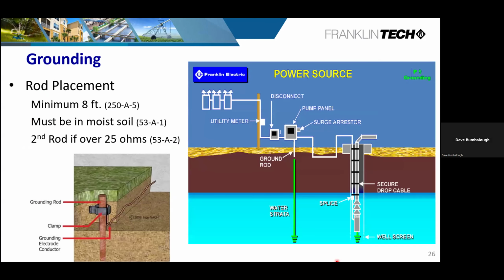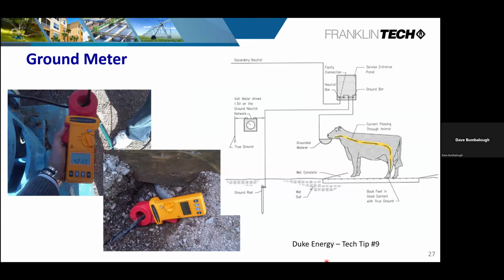So, proper grounding. I always try to make sure that there are ground rods out there, and that clamps are actually clamping and not broken or missing. Again, what I try to point out here is that our submersible pump casing is in a water strata. That's the best ground rod you're ever going to have. We don't want that. We want to make sure that the ground rods are serving their purpose, doing what they're supposed to. If they're not, then we're going to see a lot more failures over the years.